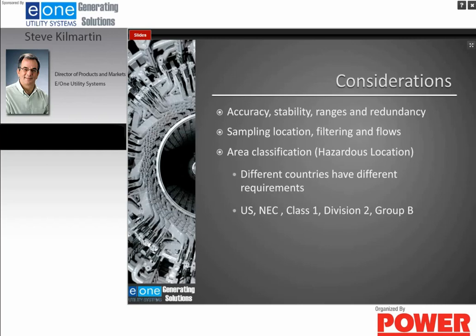As far as requirements, different countries have different requirements. In the U.S., most power plants will go by the National Electrical Code for a Class 1, Div 2, Group B piece of equipment. In Europe, it would have to meet an ATEX requirement. In Australia, it might be IECEx. So the country that you're in will determine the area classification that the piece of equipment needs to satisfy.